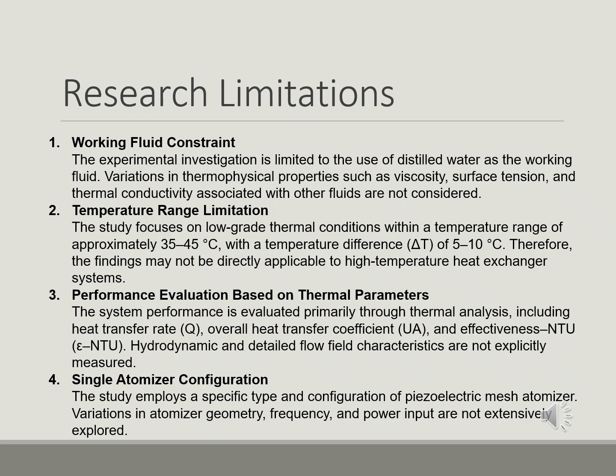Second, the study focused on low-grade thermal conditions within a temperature range of approximately 35 to 45 degrees Celsius, with a temperature difference of 5 to 10 degrees Celsius. Therefore, the findings are specifically relevant to low temperature heat recovery systems and might not be directly applicable to high temperature heat exchanger systems.